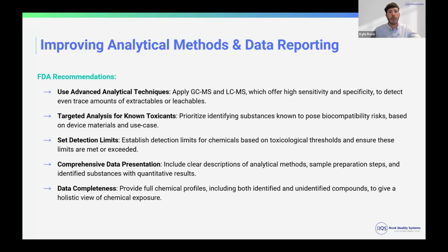So for the recommendations specifically on these analytical methods and data reporting, use the methods that apply most for your device, so GC versus LC, specifically for what type of chemicals you're looking for, using targeted analysis for known toxicants. So looking at the materials that you're using and knowing what potential substances might pose biocompatibility risks, and then searching for these with targeted analysis for your toxicants, setting detection limits for these chemicals to ensure that they meet the limits or thresholds if these are already defined.